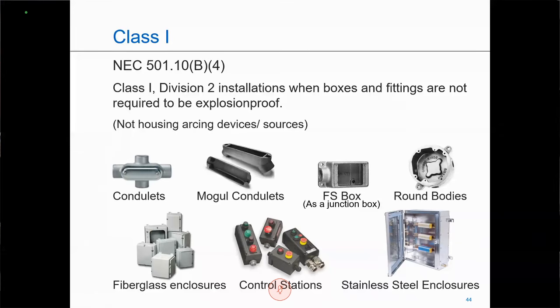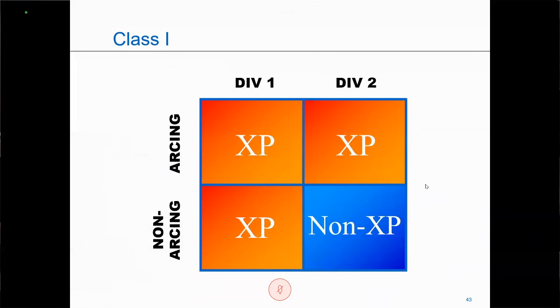Or there may be times that you see products such as control stations where a manufacturer might say this product is Class 1 Division 2 and it's in a non-metallic housing or a stainless steel housing, a housing other than the traditional explosion-proof NEMA 7 housing. That's because they've used an encapsulated or factory sealed contact block. When you do that, it takes the item from being here and drops it down here, just being concerned with the terminals. And so that's why that item doesn't have to go in the explosion-proof housing. And that's only Division 2, not Division 1.